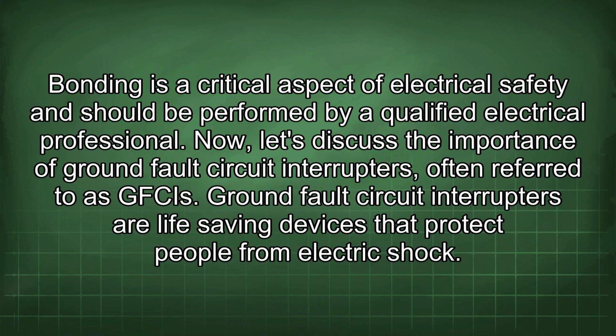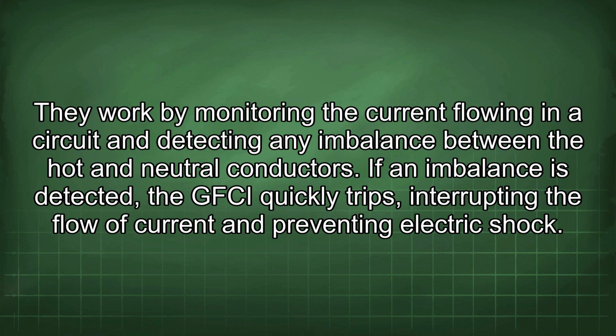Now, let's discuss the importance of ground fault circuit interrupters, often referred to as GFCIs. Ground fault circuit interrupters are life-saving devices that protect people from electric shock. They work by monitoring the current flowing in a circuit and detecting any imbalance between the hot and neutral conductors. If an imbalance is detected, the GFCI quickly trips, interrupting the flow of current and preventing electric shock.